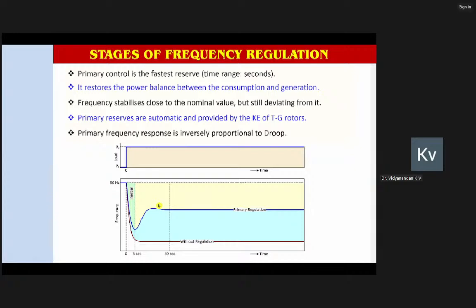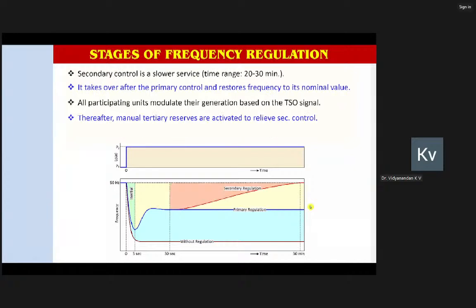So as long as there is a steady state deviation, that deviation will be integrated. Integration means it will be added till that deviation becomes zero. So after about 20 to 30 minutes in certain cases, or maybe 10 minutes in the latest units, finally your frequency will come back to the nominal 50 hertz. This is what happens in our machine through the governor action.